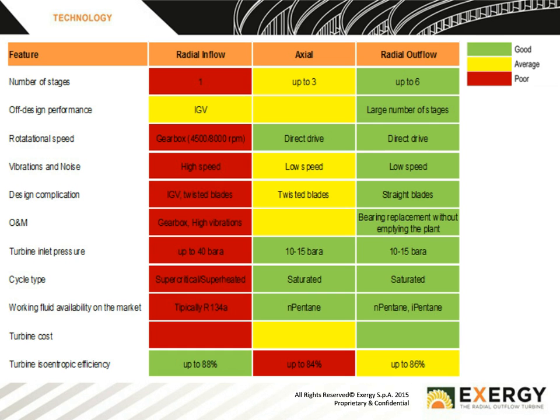Vibrations and noise. Again, I've already mentioned to you that the low vibrations of our turbine gives a significantly longer bearing life and really helps the maintenance of the unit. The high-speed turbine obviously is affected by some noise and also by wear on the bearings because of the high speed, and the axial will have higher vibrations.